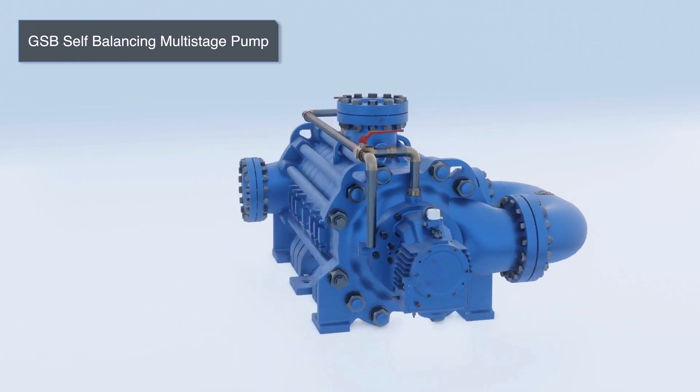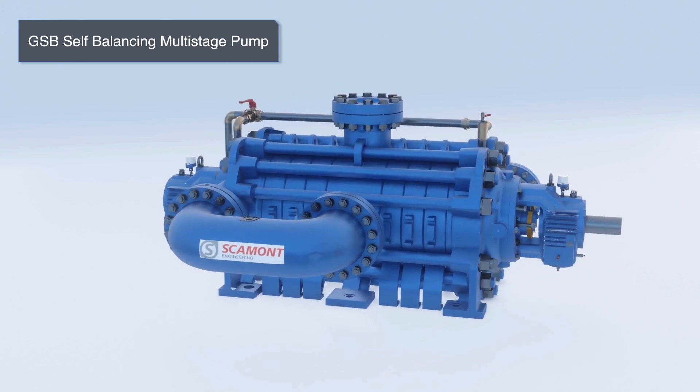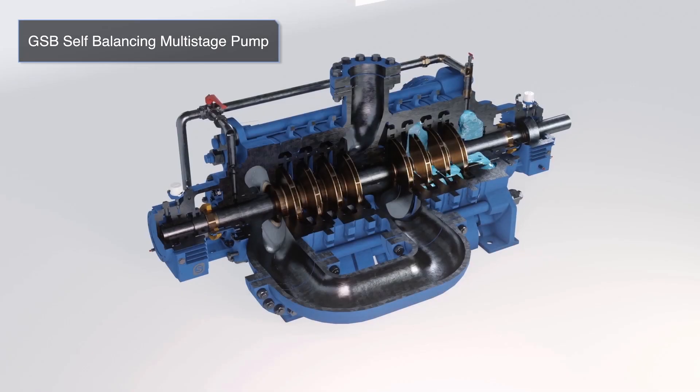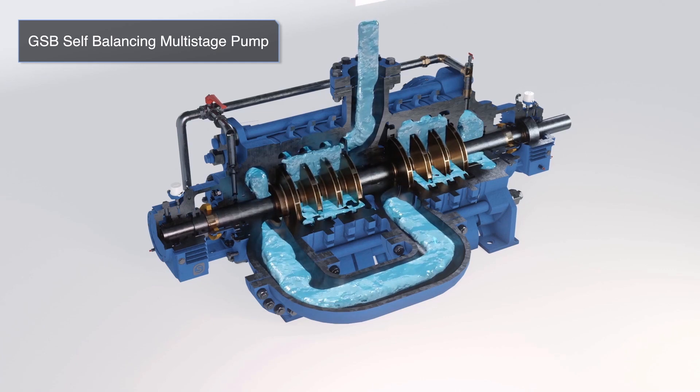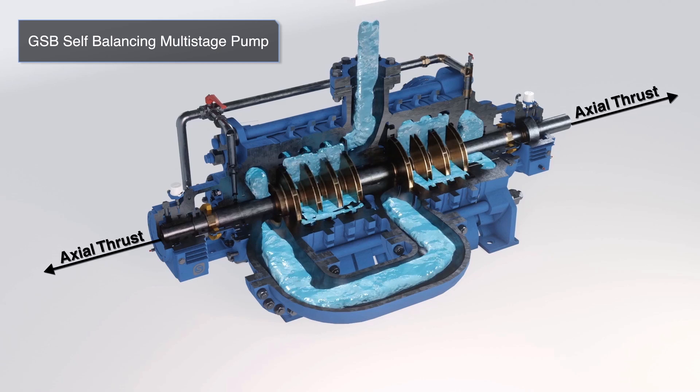In the SDM, the self-balancing multi-stage centrifugal pump known as the GSB is utilized. As the name suggests, these pumps are self-balancing and therefore do not require a balance disc assembly to overcome the axial thrust as seen in typical in-line multi-stage pumps. These pumps are designed for high pressure and high flow rate applications.